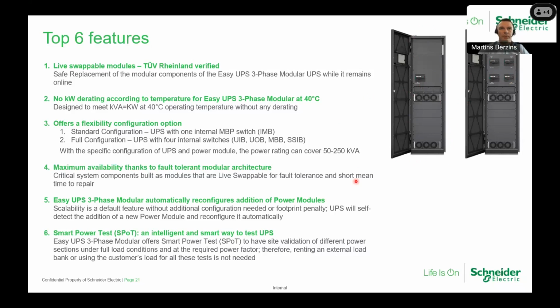So thanks to this live swap capability, it's a highly fault tolerant modular architecture. Once adding the power modules or scaling up, the UPS will self-detect the addition of new power modules and reconfigure automatically. And the load in all the power modules is shared equally among all the power modules. Also we have implemented smart power test, which is a very intelligent and easy way to simulate and test the UPS without using the load bank. Basically, this spot mode or smart power test simulates the conditions when the UPS is 100% loaded without adding the load bank.